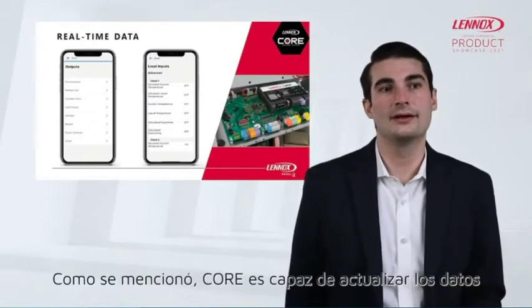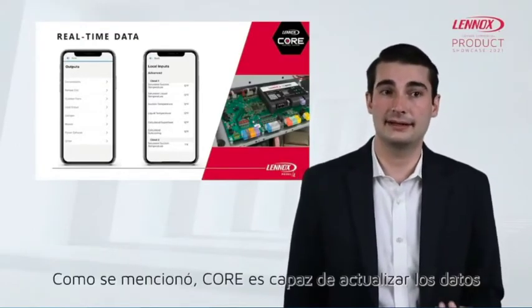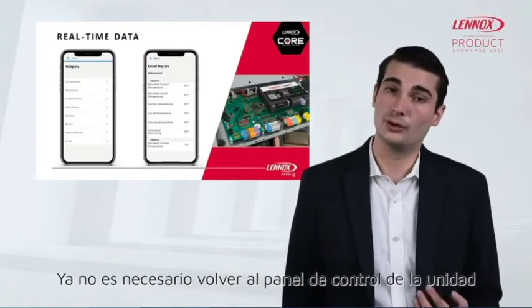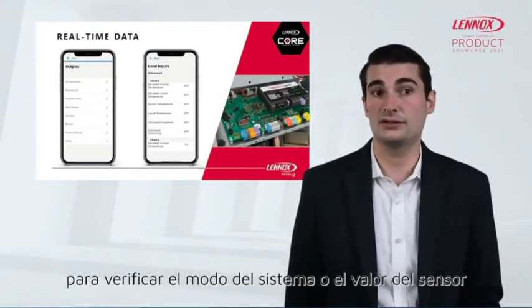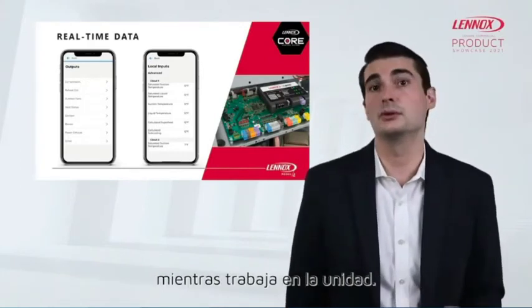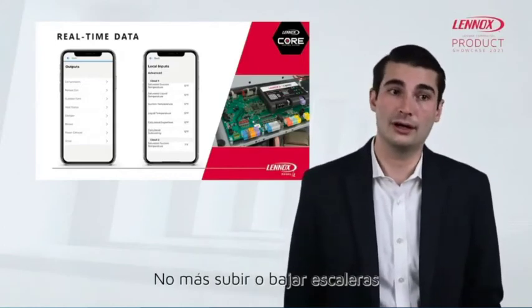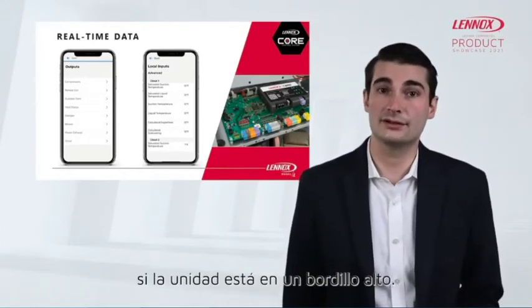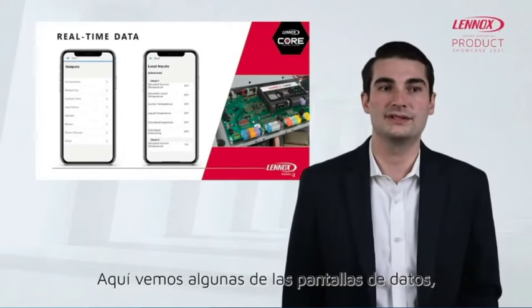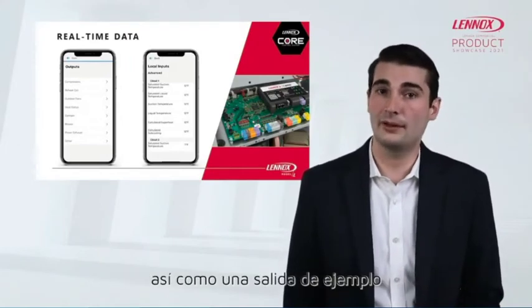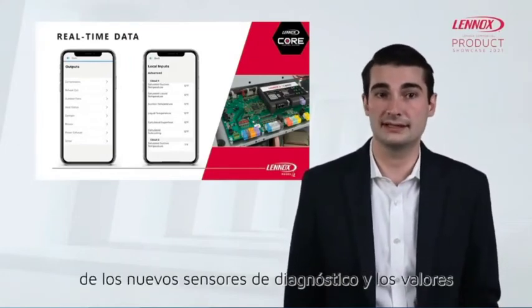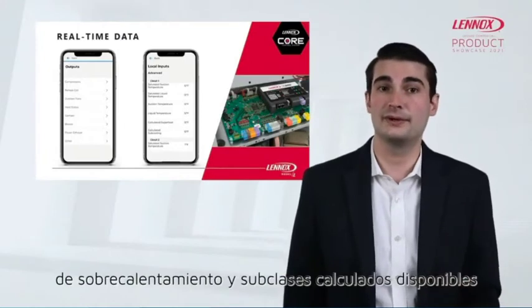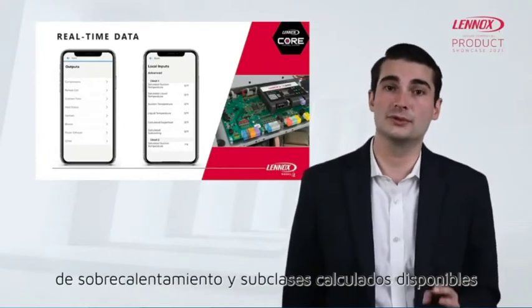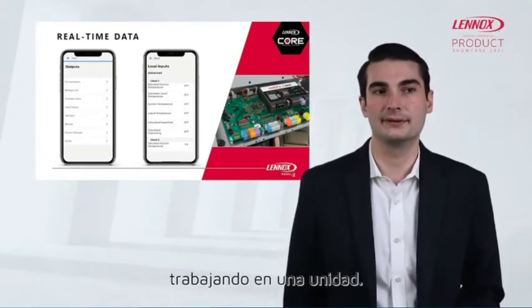As mentioned, Core is capable of updating data to the app in real time. No more returning to the control panel of the unit to check a system mode or a sensor value while you're working on the unit. No more up or down on ladders if the unit is on a tall curb. Here, we see some of the data screens, as well as an example output of the brand new diagnostic sensors and calculated superheat and subcooling values available directly on the app while you're working on a unit.